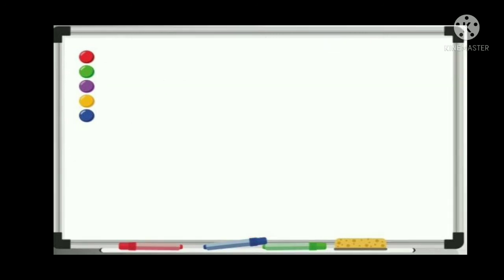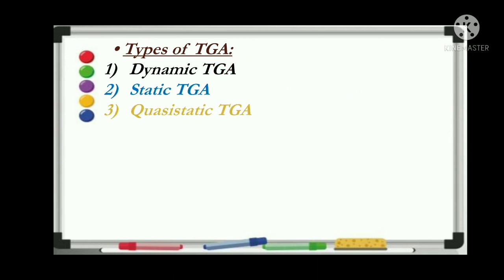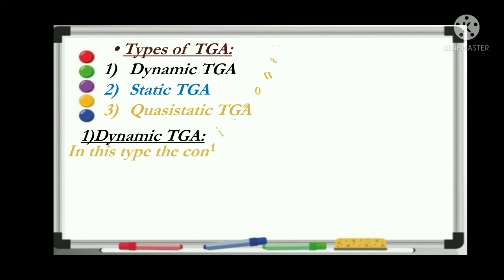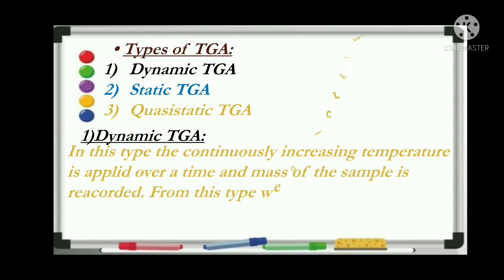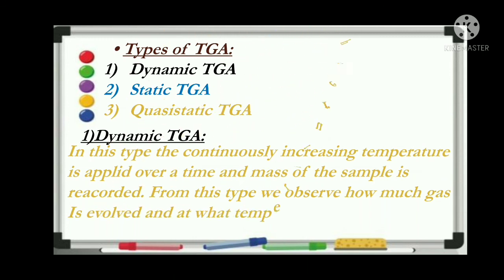Now let's see the classification or types of thermogravimetric analysis. TGA is classified into three types: first is dynamic TGA, second is static TGA, and third is quasi-static TGA. In dynamic TGA, the name itself indicates that we apply temperature to a sample in increasing order, and as the temperature increases, the change in mass of the sample is recorded. From this method we can determine how much gas is evolved from the solid and at what temperature the gas is evolved.